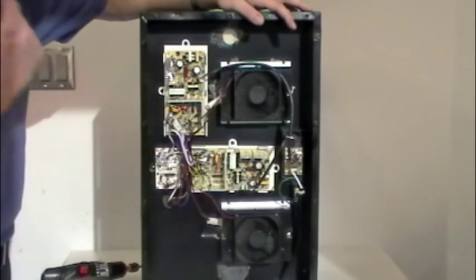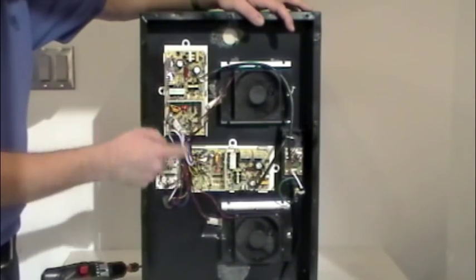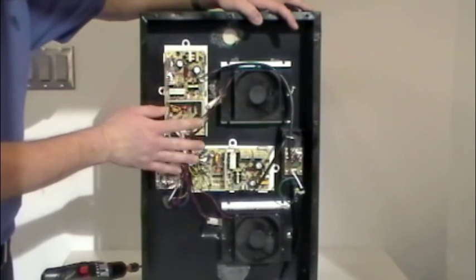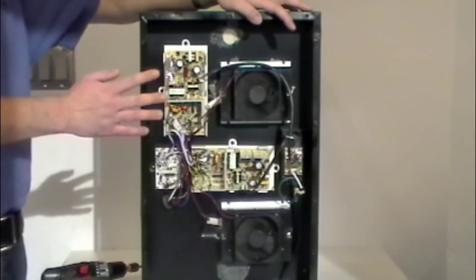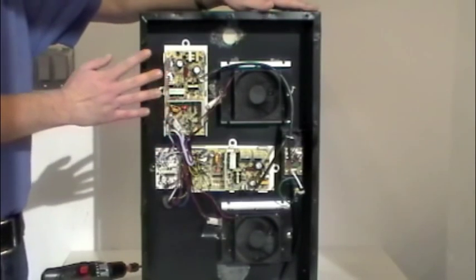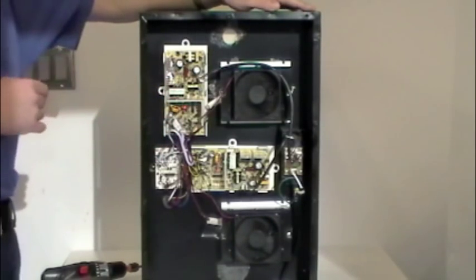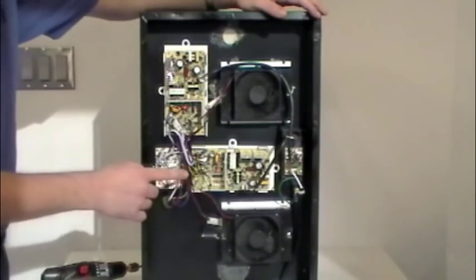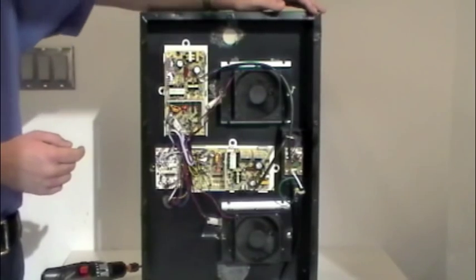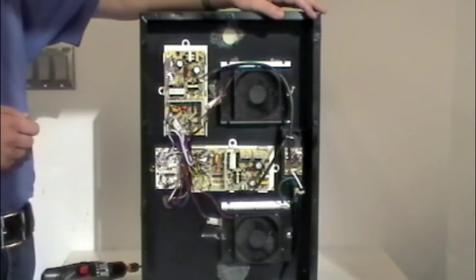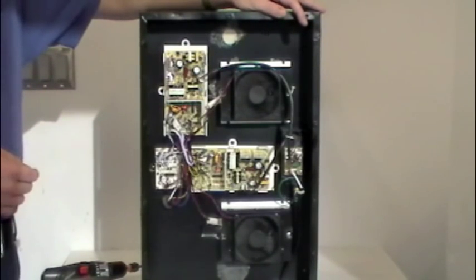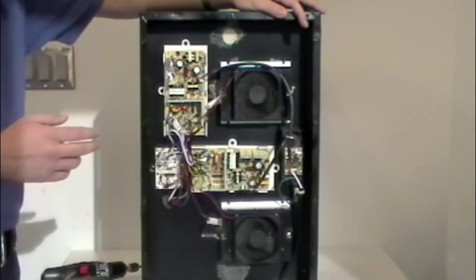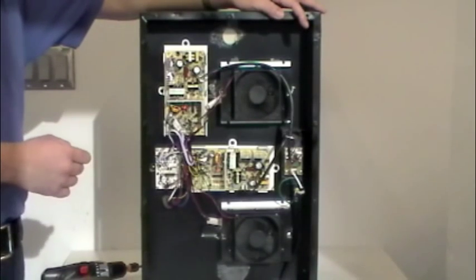Circuit boards, which are basically the heart of the unit. These boards are identical. They're just in different positions. Those boards are susceptible to a lot of things. We need to make sure that we ground ourselves and discharge any static electricity. You might want to wear an ESD strap just to protect yourself. The boards basically only have one failure mode. They either work or they don't. As you can see there's a couple of LEDs in here. One of them is green and one of them is red. There's one on each board. Red would indicate the power is being applied to the board.